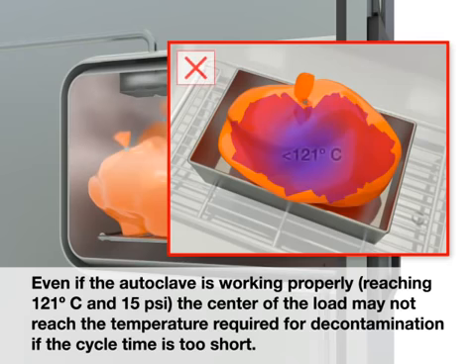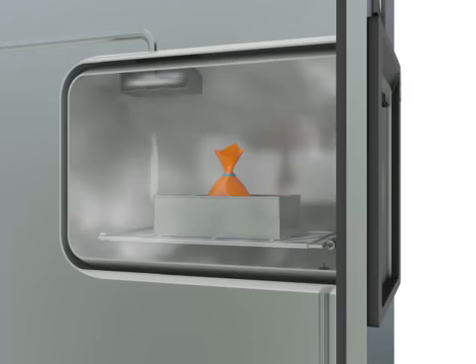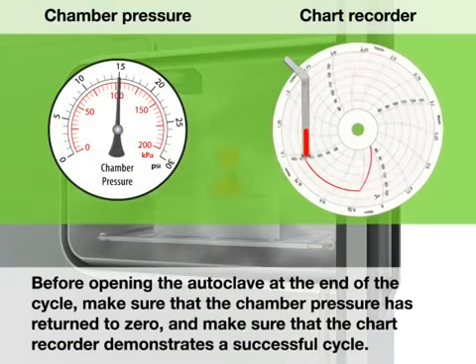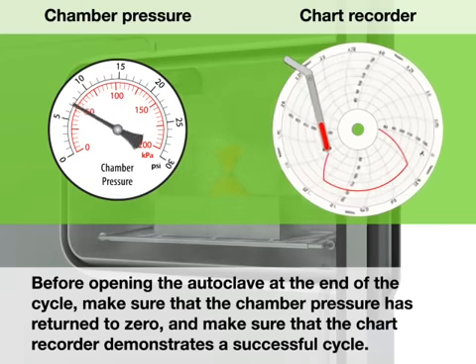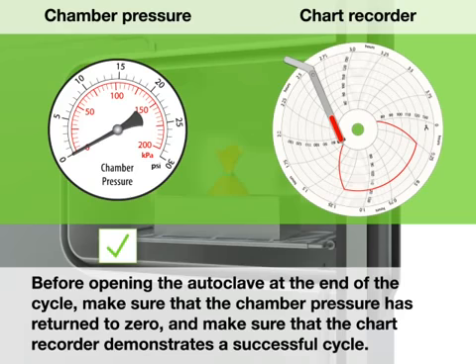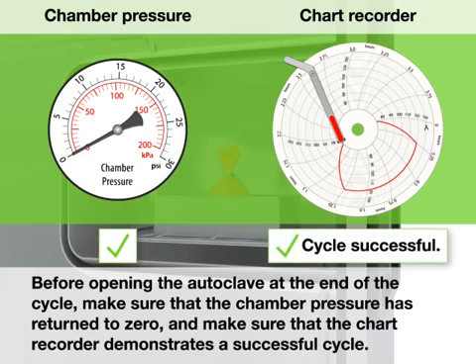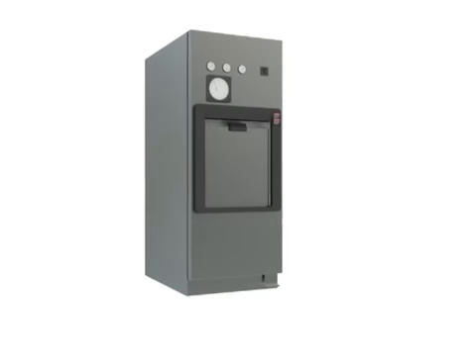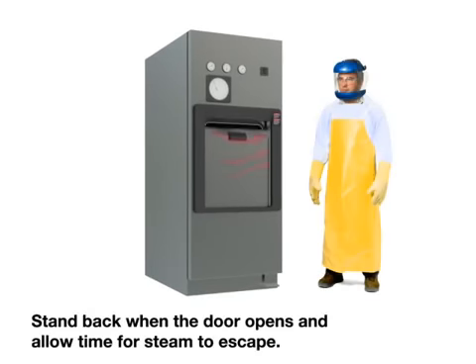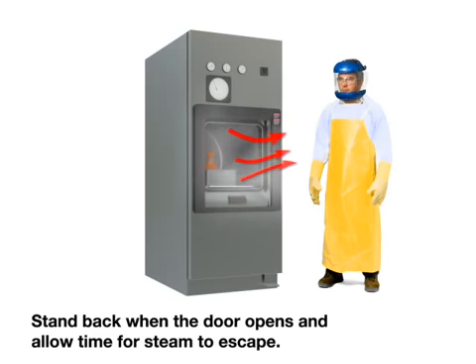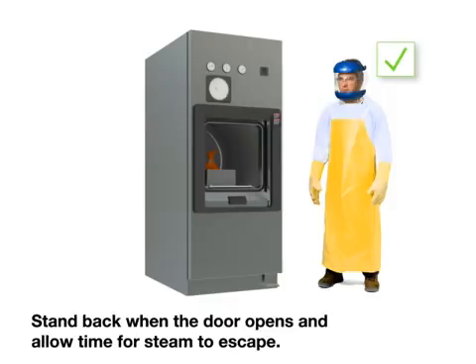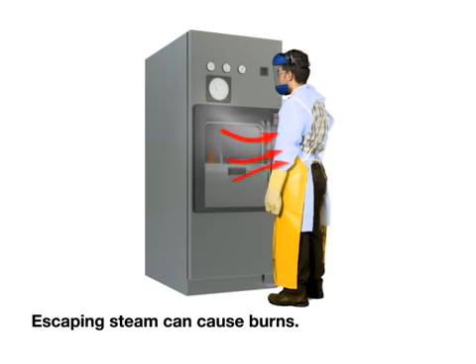Even if the autoclave is working properly, reaching 121 degrees Celsius and 15 psi, the center of the load may not reach the temperature required for decontamination if the cycle time is too short. Before opening the autoclave at the end of the cycle, make sure that the chamber pressure has returned to 0 and make sure that the chart recorder demonstrates a successful cycle. Stand back when the door opens and allow time for steam to escape. Escaping steam can cause burns.